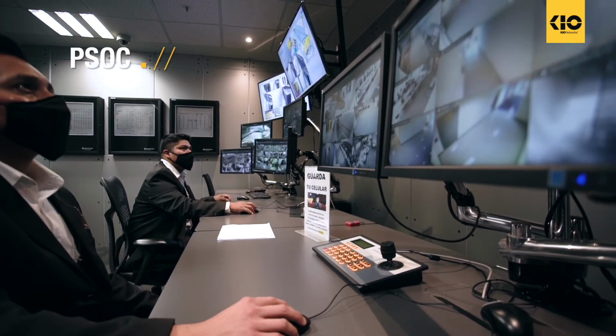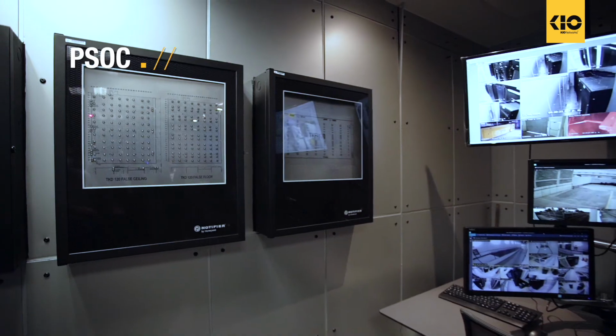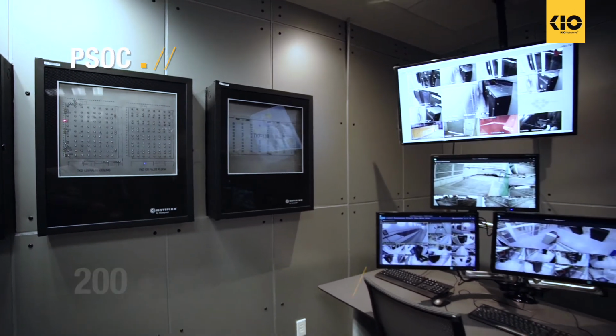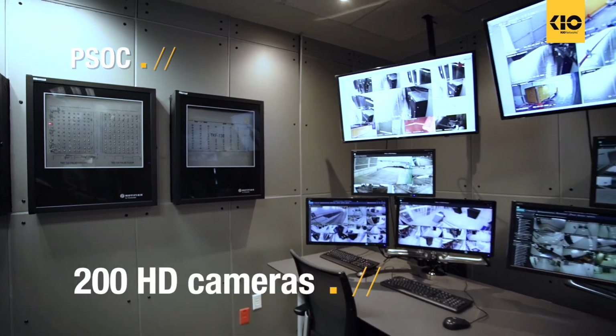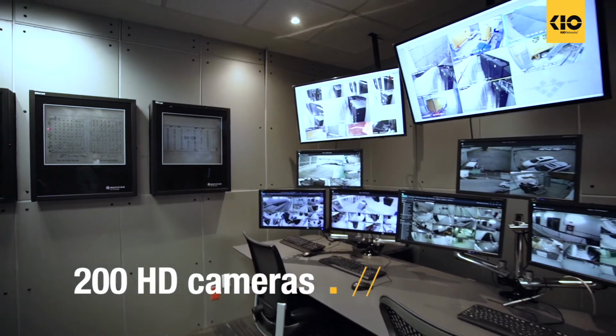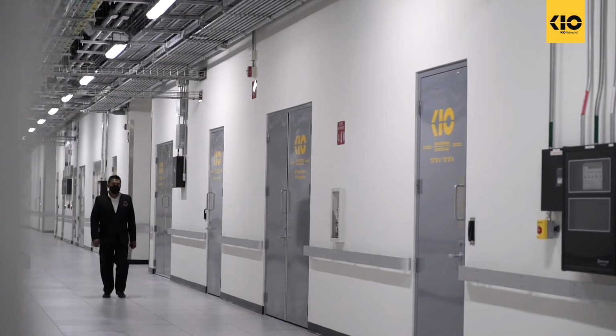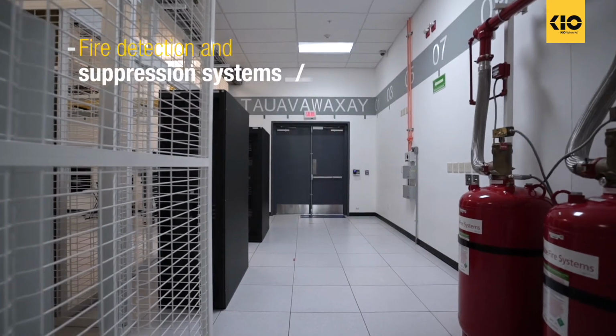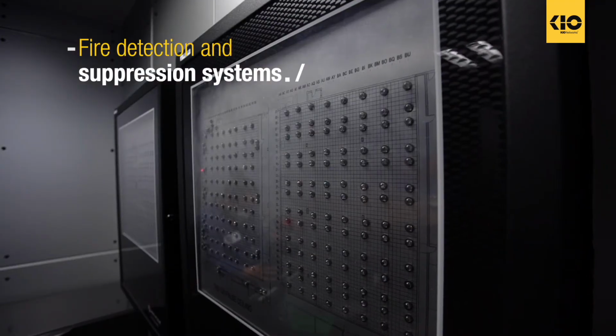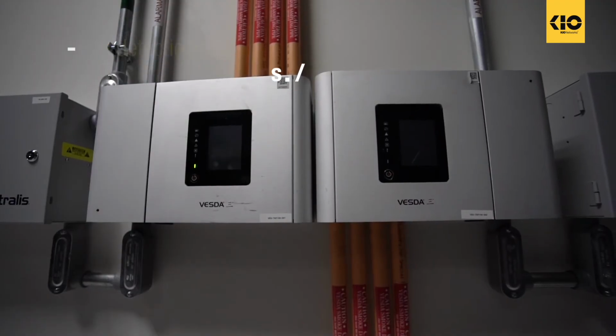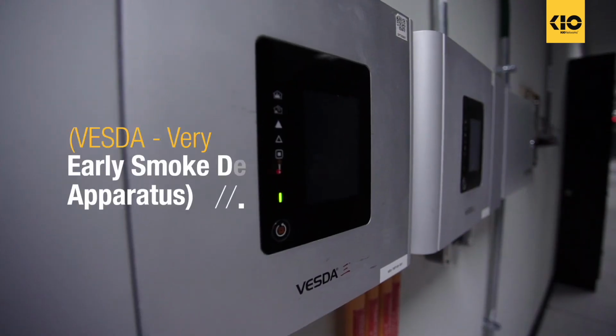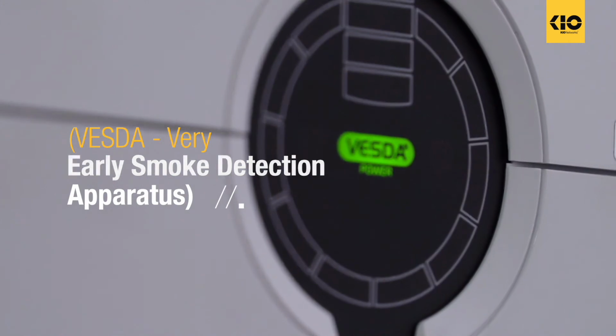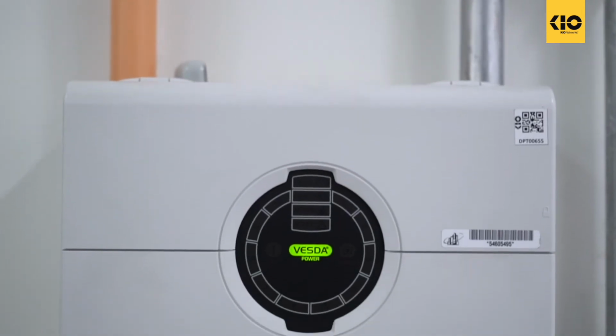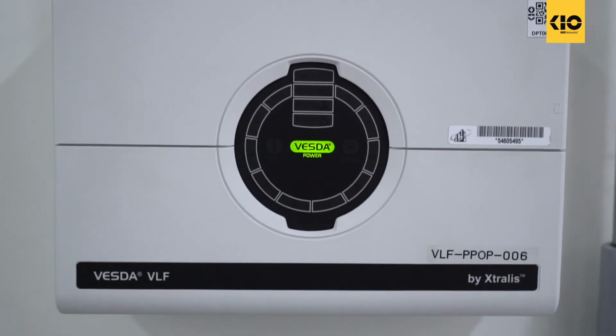24/7 on-site and remote monitoring of facilities from the Physical Security Operating Center with about 200 HD cameras with a recording of more than 90 days. Periodic tours of the security guards throughout the building. To safeguard people and the hosted infrastructure, the data center has the following elements. We equip our buildings with VESDA early fire detection monitoring systems, which allow us to detect an outbreak of fire hours before it becomes critical.